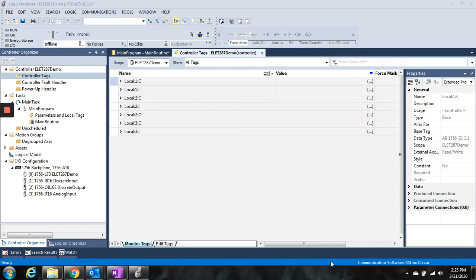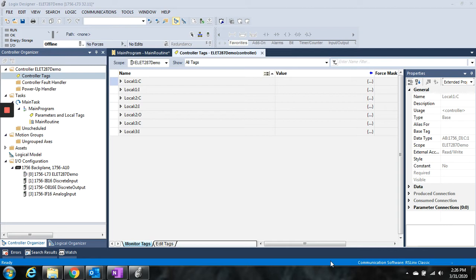What we've been doing and what you're used to doing with the Siemens has been addressing based on memory location. So we did like a %I0.1, and that referred to the %I table being the input table. 0.1, so 0 would have been byte 0, and 1 would have been bit 1. So we could map that I/O point to the memory table based on that address.